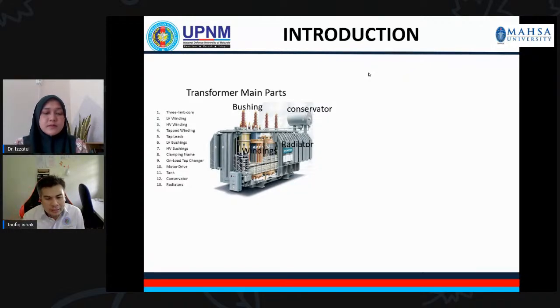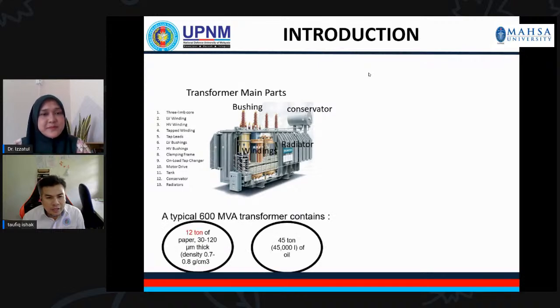Then we have a conservator, which is where the excess oil of the transformer will flow. We have a radiator to cool the transformer. The most important part is the winding. Transformer winding includes the paper insulation that is wound around the transformer.